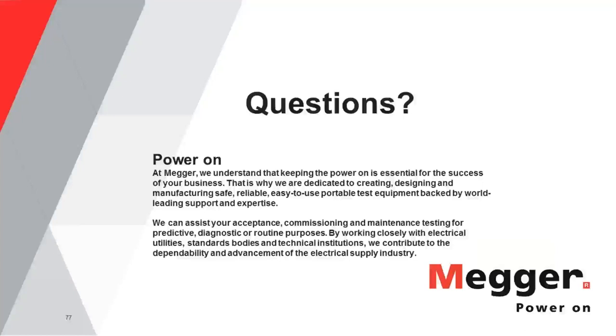All right, thank you, Jeff. I have another question for you, Jeff. IEEE 43 says that readings above 5G on a motor, generator, etc., are greatly affected by factors other than insulation resistance, and therefore PIs are not recommended as an assessment tool in this case. What are your thoughts on this?